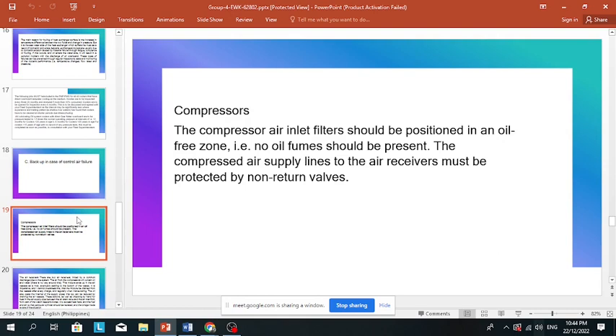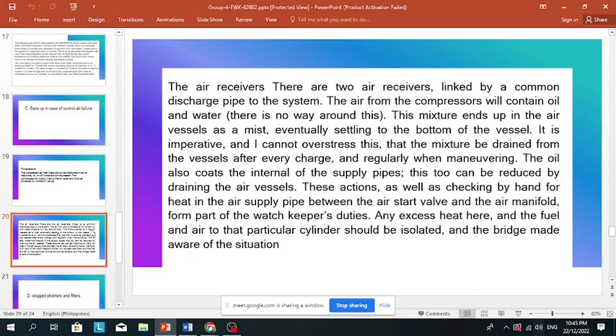Next, the air receivers. There are two air receivers linked by a common discharge pipe to the system. The air from the compressors will contain oil and water. There is no way around this. This mixture ends up in the air vessels as a mist, eventually settling to the bottom of the vessel.